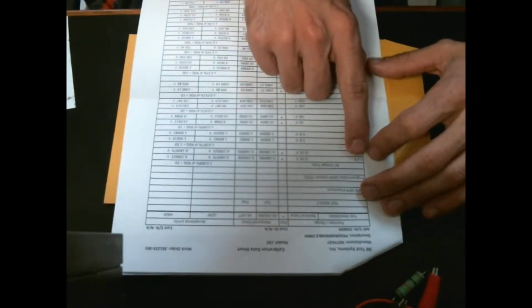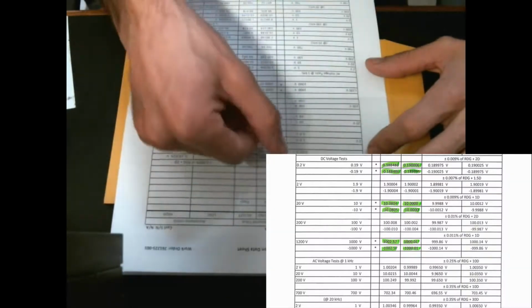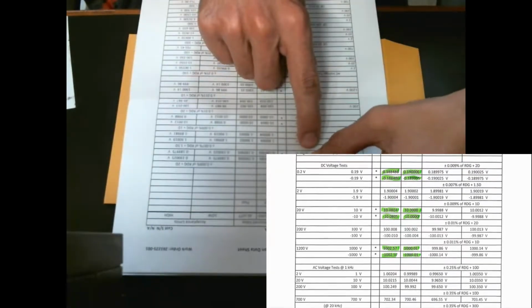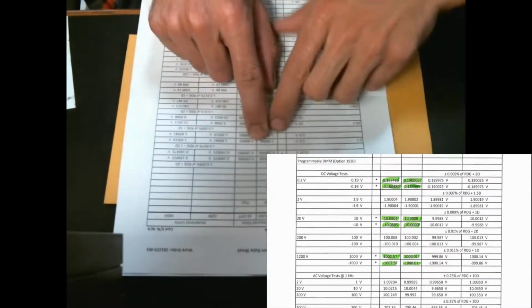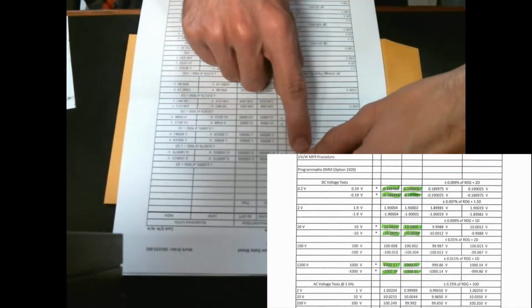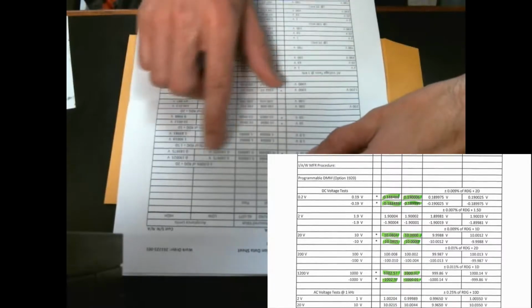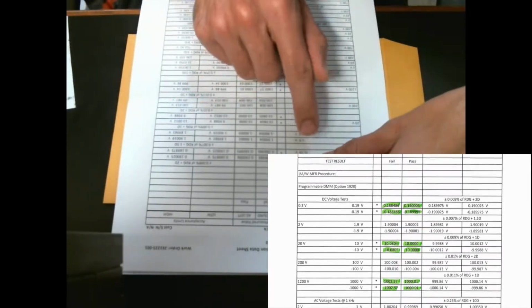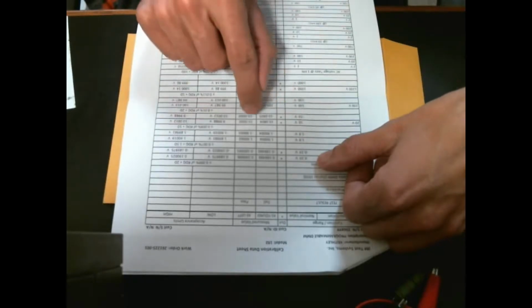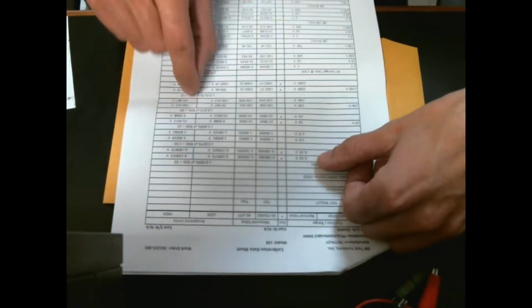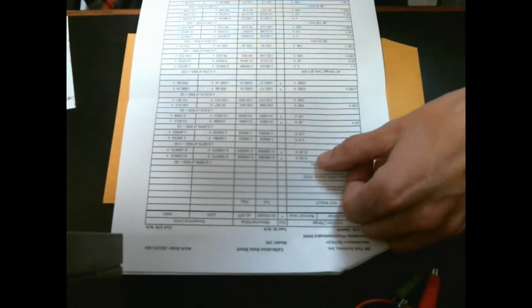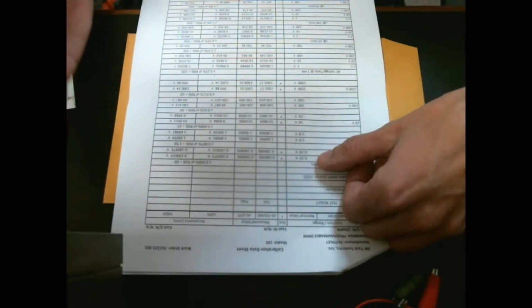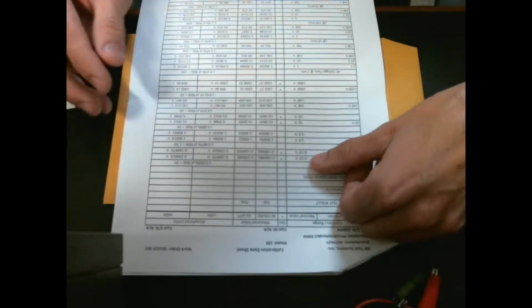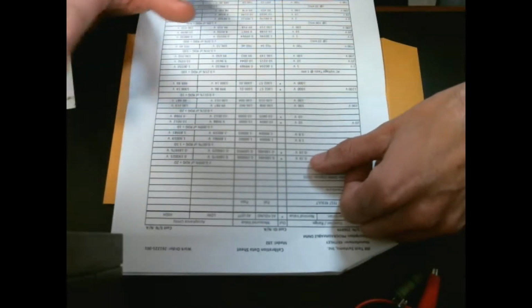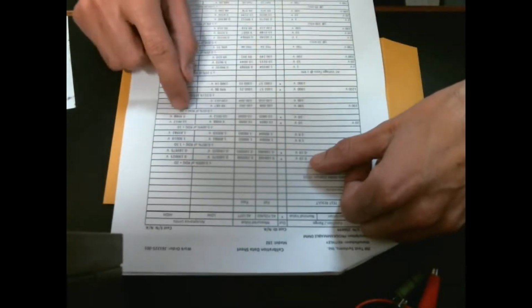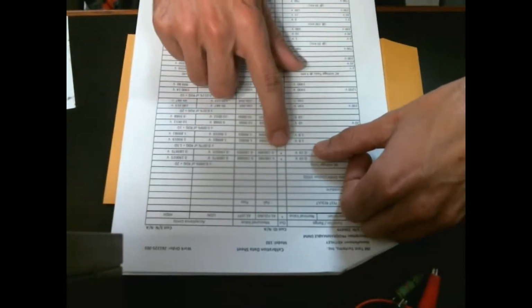And then you see here it starts off each range with the 0.2 volt, and they test it at 0.19 volts. And they don't go decimal places way out to show the 6.5 digits, because they're using a voltage standard that is going to be absolute 0.1900000 past the 6.5 digit resolution of the Keithley. They could probably go to 8.5 digit and then they would start getting some drift, but 6.5 digits is going to be dead on 0.19 volts. So they just saved that.